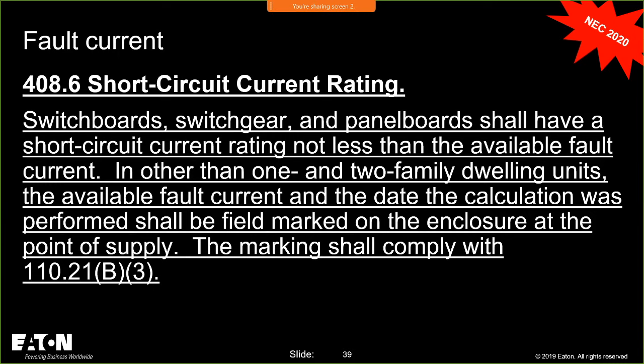So the key thing here is, and it's dawning on me, that there's no requirement in 408.6, which is where it would be, that says it has to be marked with its short circuit current rating, but it does say it has to be marked with the available short circuit current. I could be wrong, unless somebody out there knows somewhere else in 408 that says it's marked, but I'm not seeing it. I could be missing it.